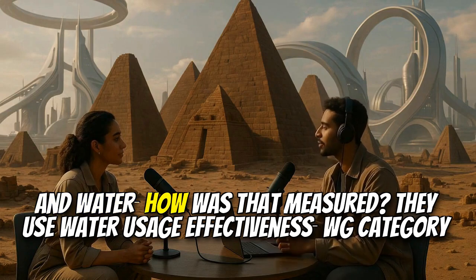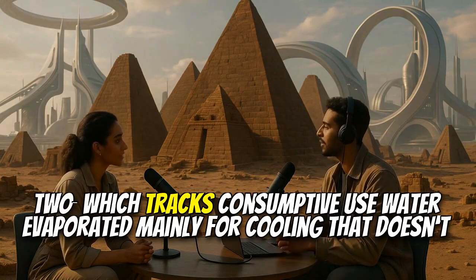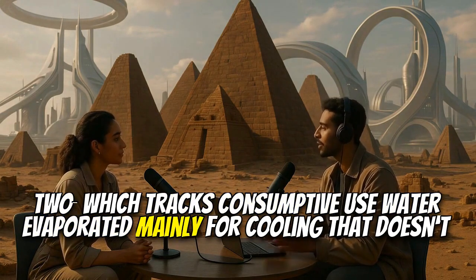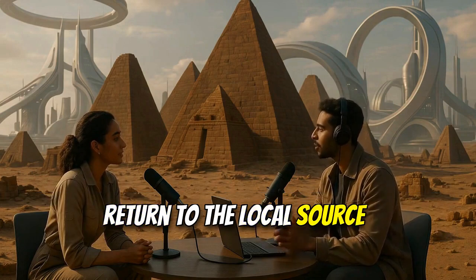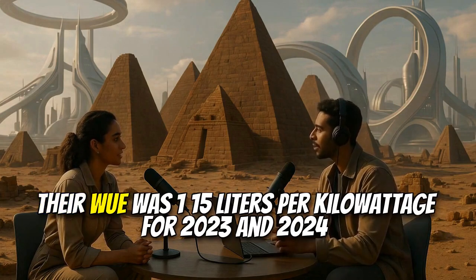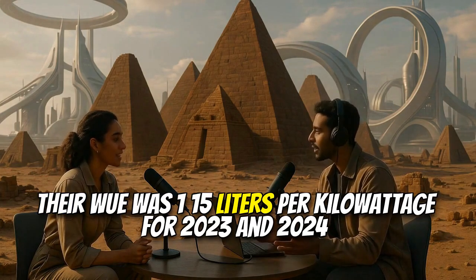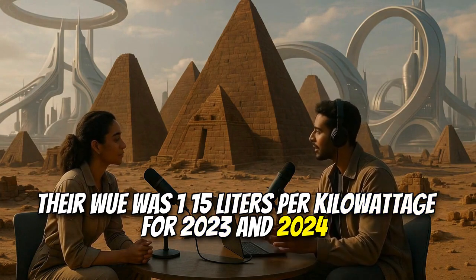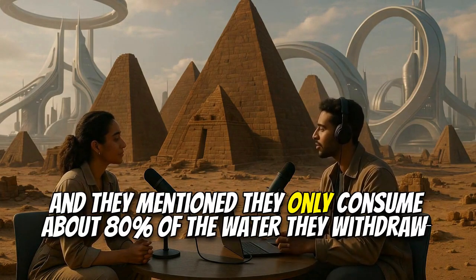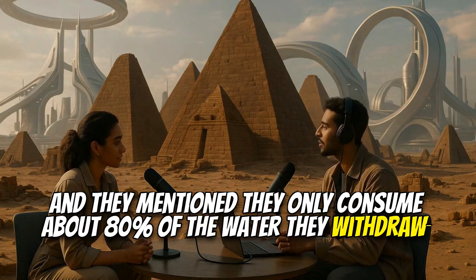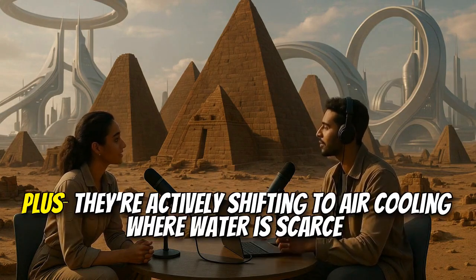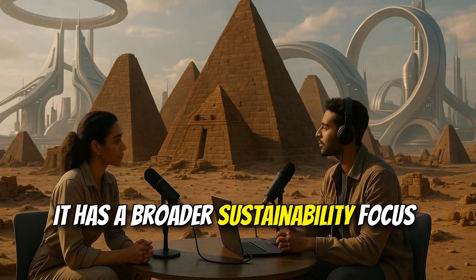And water, how is that measured? They use water usage effectiveness, WUE category 2, which tracks consumptive use, water evaporated mainly for cooling that doesn't return to the local source. Their WUE was 1.15 liters per kilowatt-hour for 2023 and 2024. And they mentioned they only consume about 80% of the water they withdraw, suggesting good management. Plus they're actively shifting to air cooling where water is scarce, which has a broader sustainability focus.